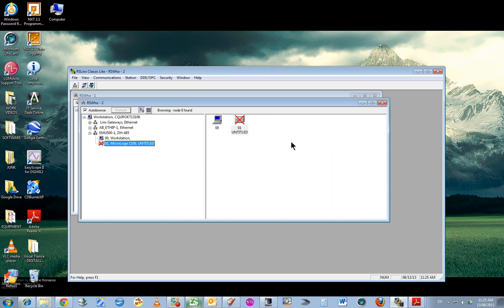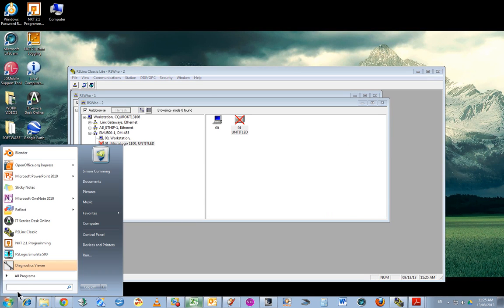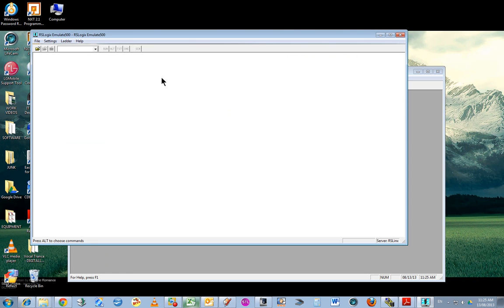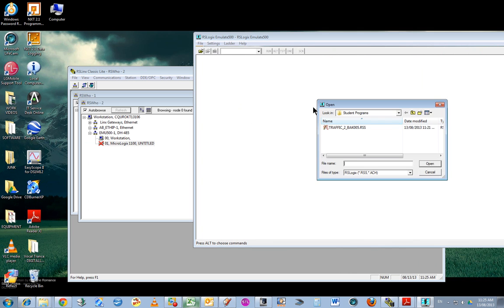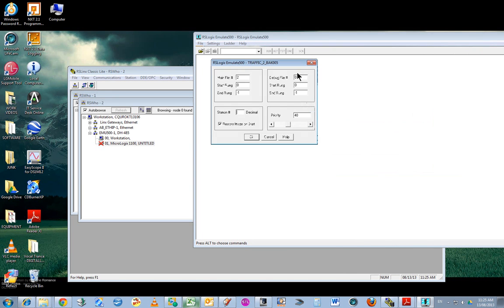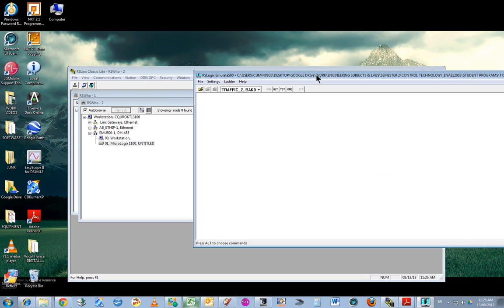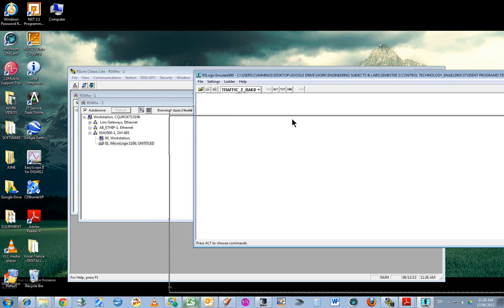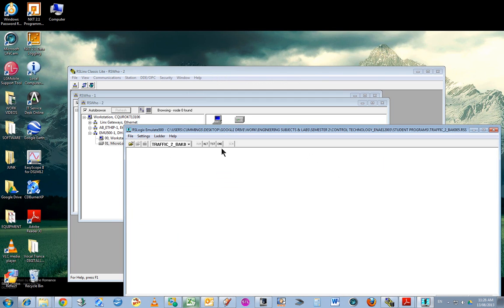Now you can see that's got a little red box through it, which means the emulator program is not running. If I start RSLogix Emulate 500, I can open up a program, give it a station ID, and run. You'll see that little red cross is gone now. Once I've started that process, the virtual PLC is now visible.